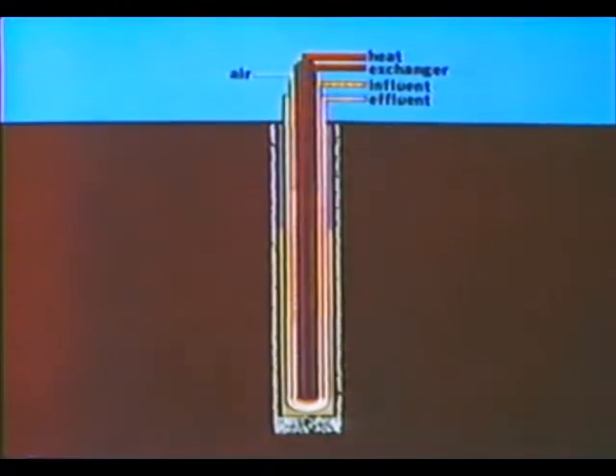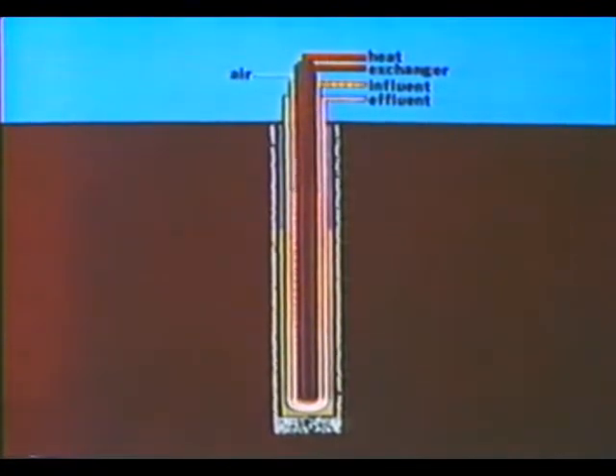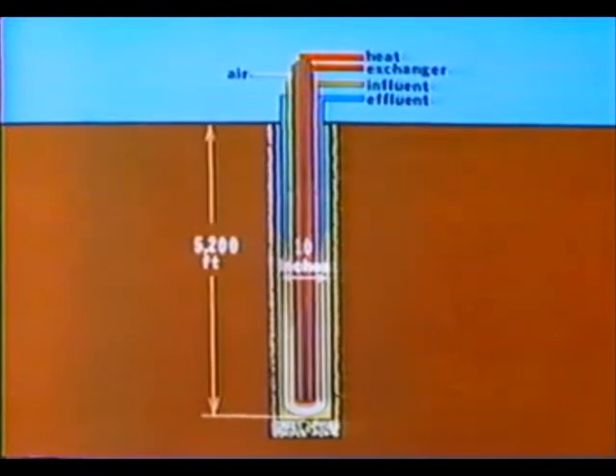Diluted waste liquid flows through the inner annular space of the concentric vertical tubes and returns in the outer annular space. Use of this vertical tube configuration has multiple purposes. The waste stream and injected air flow down the tube and reach a peak natural pressurization of 1,500 pounds per square inch at the bottom due to the height and density of the fluid above. Diameter and length are designed to provide sufficient residence time so that the oxidation reaction can be completed. In addition, the high length to diameter ratio allows extremely efficient counterflow heat exchange and mass transfer.